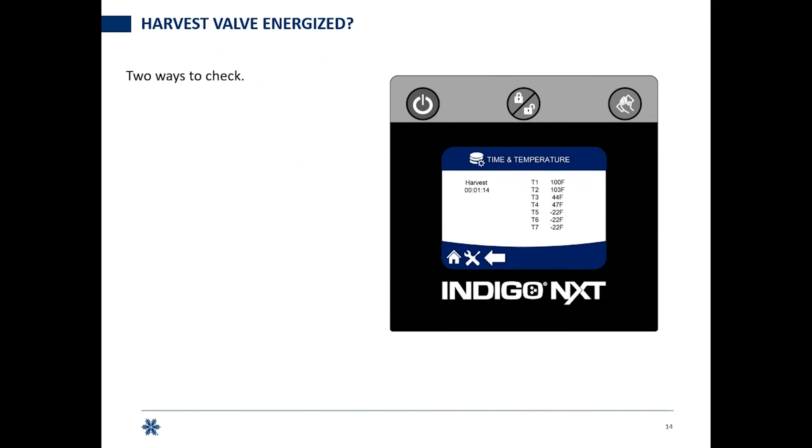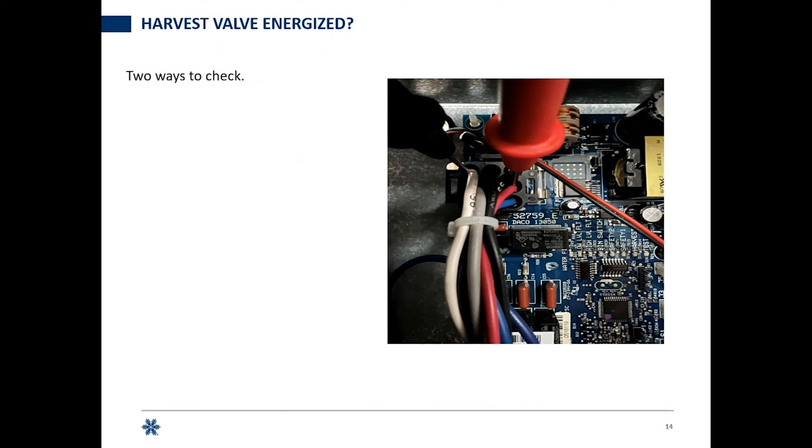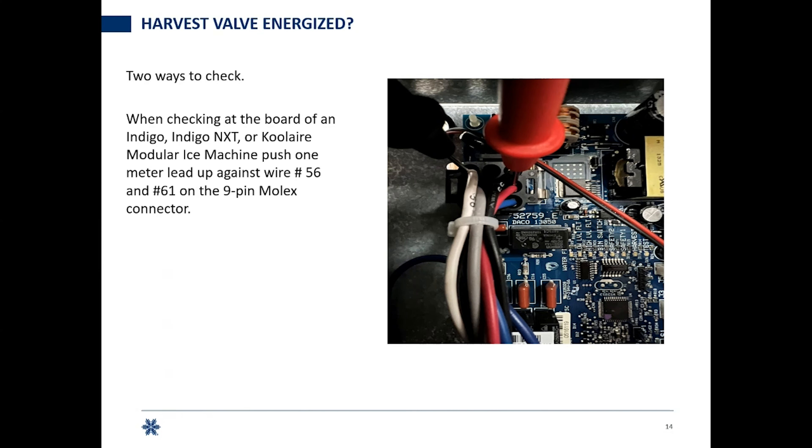The harvest valve — is that valve energized? There are two ways to check. First, especially with an Indigo Next with a digital display, go into your real-time data menu to verify you're actually in harvest. You can check at the valve itself — put your leads on the exposed metal part of the solenoid and you should have line voltage across that valve during harvest. You can also check at the board: on a Koolaire board, go across wire 61 with your red lead and wire 56 with your black lead — that's L1 on 61 and neutral on 56. It's the same wire numbers on an Indigo Next or Indigo, even though they're different boards.